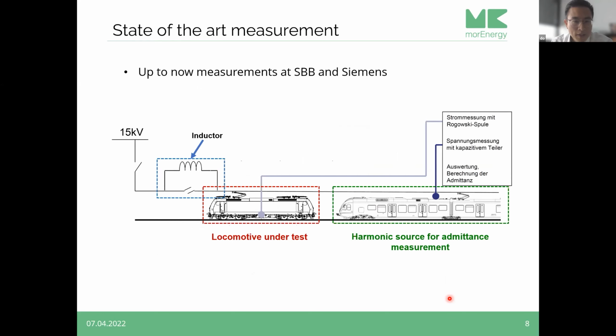What is state of the art? In practice, the measurement setup is realized as you can see here on this picture. In the red pointed line, you can see the device under test. Then you have another traction unit that is modified as a harmonic source. This traction unit feeds harmonic voltages into the grid and excites the system, and then by measuring voltage and current you can calculate the admittance of the device under test.